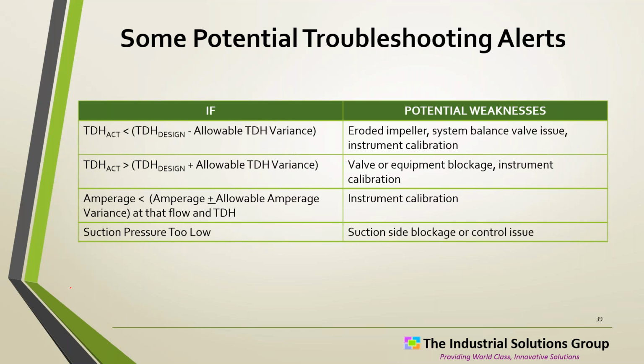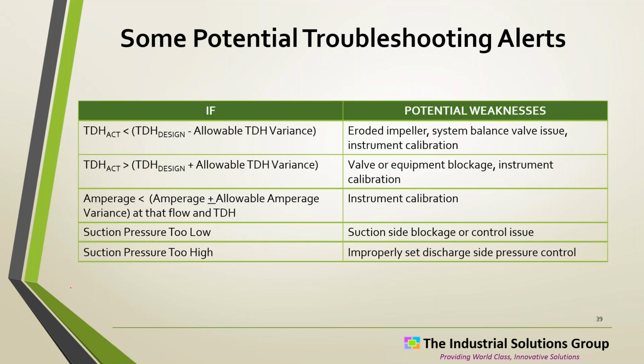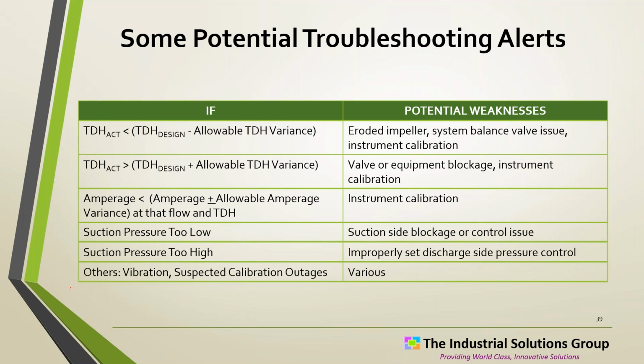Suction pressure is too low. You kind of get the point that every one of these potential alerts, again, a pump is a pretty simple piece of equipment, but you can start seeing where the complexity is. And if you don't provide the controls or at least the data for all these things, how do we expect a technician to troubleshoot properly? You could even step it up a notch. You could add vibration on real major equipment.